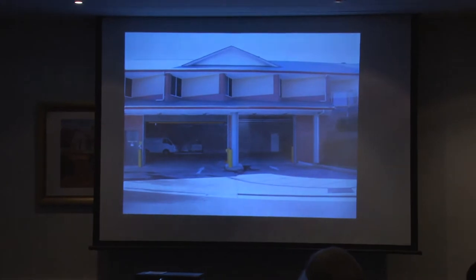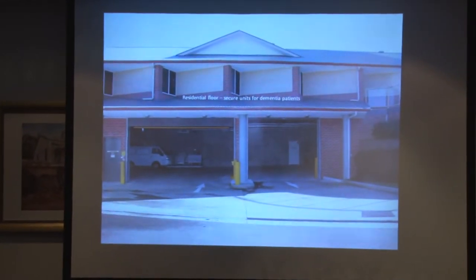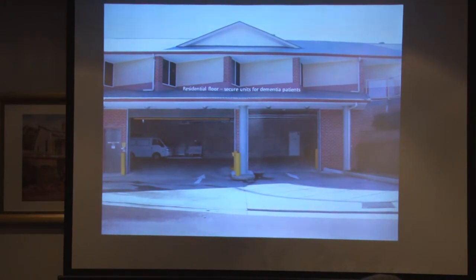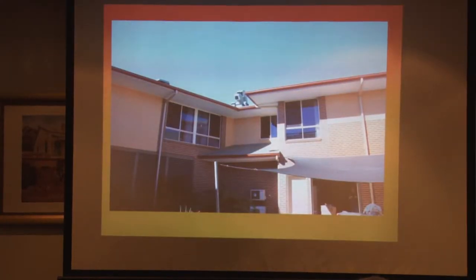The fire was actually in a nursing home. The top floor is where the dementia patients are, requiring 24-hour care. Down at the bottom you've got the laundry and the kitchens. The door to the right is where the washing room was, and behind the van is the actual drying room — two parts — with the kitchens further on. Inside the building is a courtyard. That roller door was closed during the fire, and the firefighters opened it to vent the smoke. The smoke then went up through the shaft and into the open windows of the dementia unit.